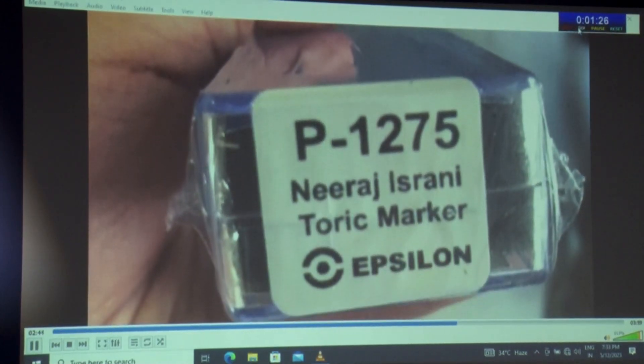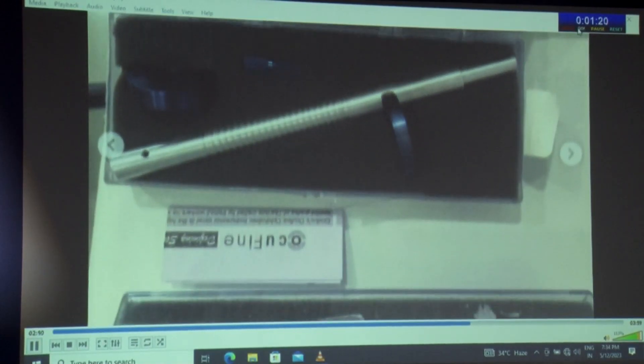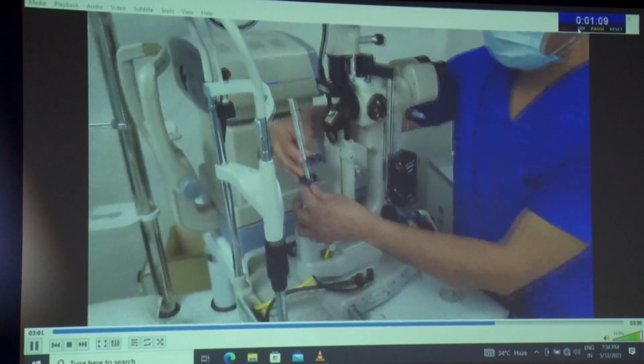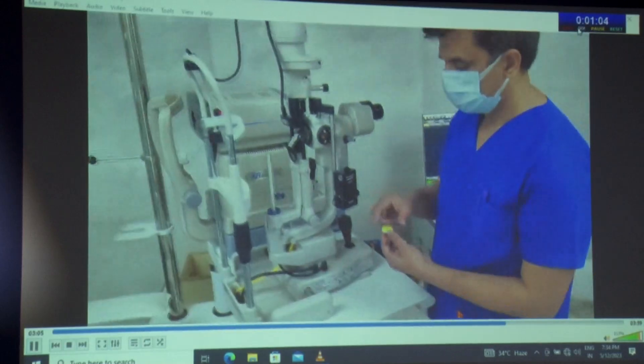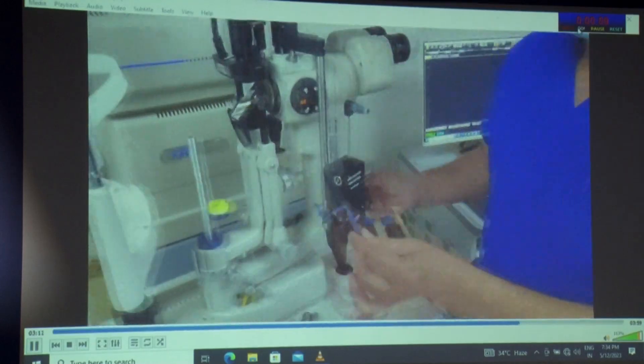STORM is now published in the Indian Patent Journal and is in the final stage of hearing as far as the patent is concerned. Thanks to Epsilon USA, we have now come up with the final product. It is made out of extremely lightweight aluminum and the marker is made out of titanium with very precise and sharp edges. The marker is placed into the calibration slot and the bubble level ensures the device is perpendicular to the slit lamp table.